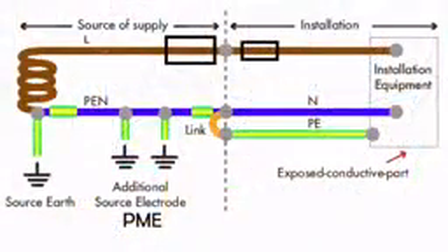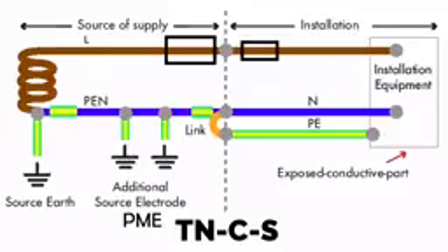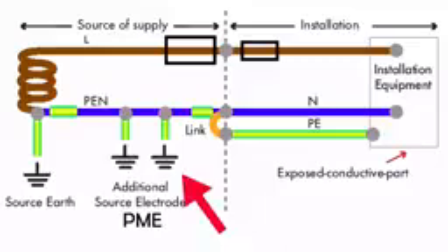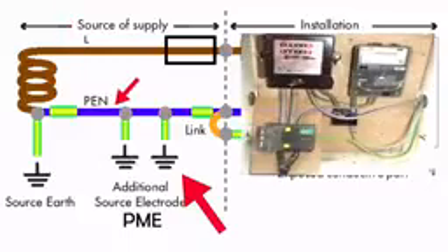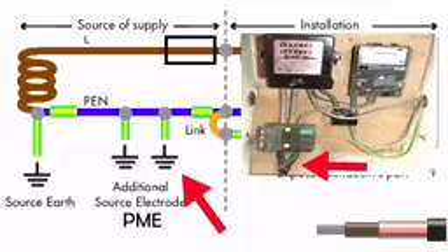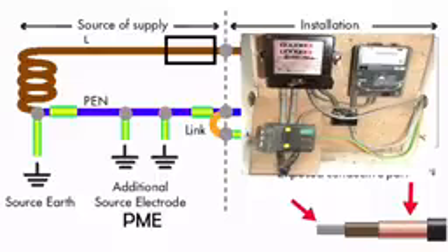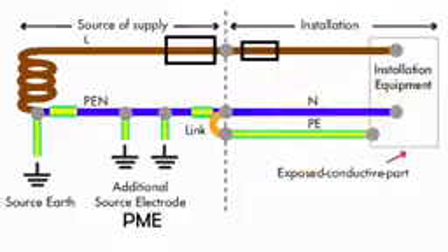The left hand side of this drawing shows the supply authority's cable. It has a separate line conductor and a combined protective earth neutral conductor. This combined cable is the one we can see coming to the bottom of our cutout. This concentric cable has a copper earth neutral and an aluminium line conductor and will enter the building normally underground but can come in overhead.